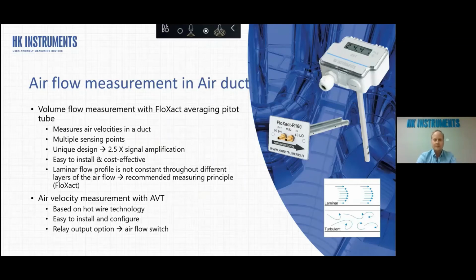And then we have another solution for the air velocity or the flow measurement in the duct. So basically this slide is showcasing both principles we can use. As mentioned in the earlier slide, something about the Floxact, which you can see in the picture, it's this kind of averaging pitot tube. And you can use it for the in-duct flow measurement. It's very easy to install because you just need to screw it on the duct, and you can have those for all the different standard sizes, but also custom made. That's not the problem.